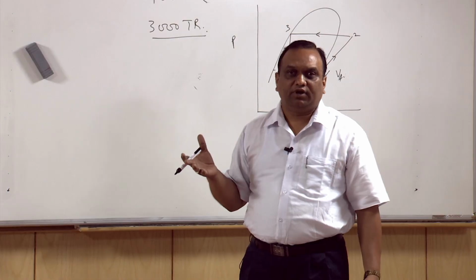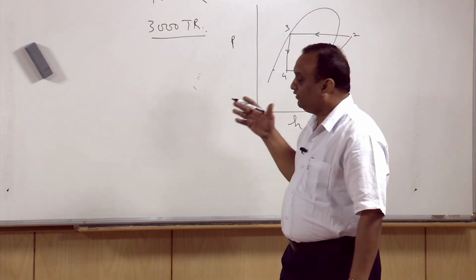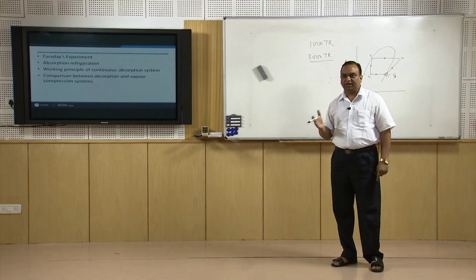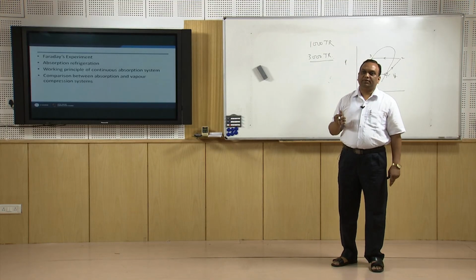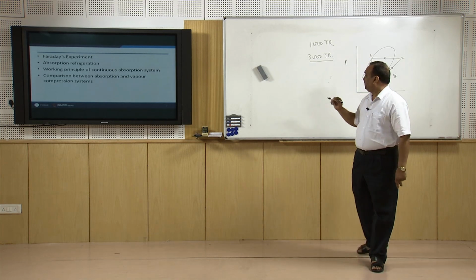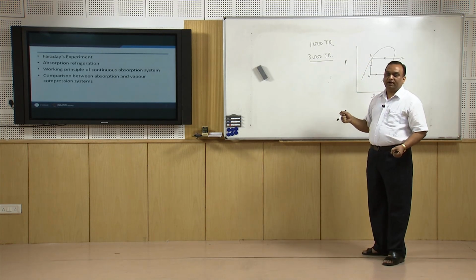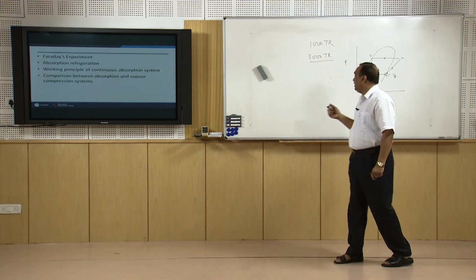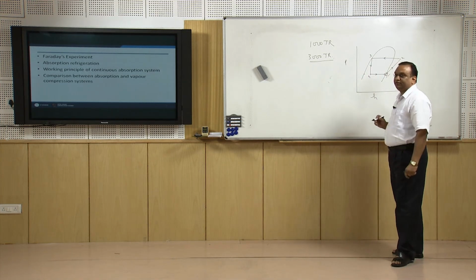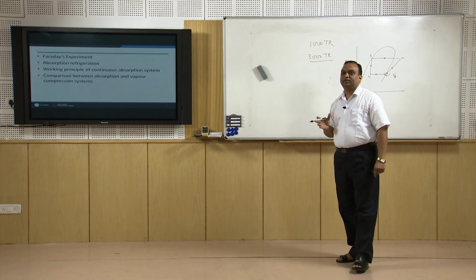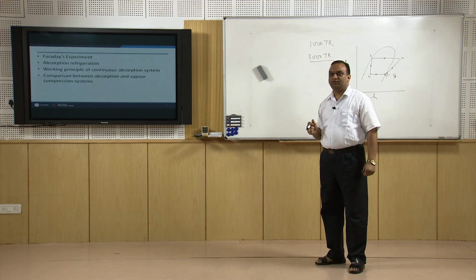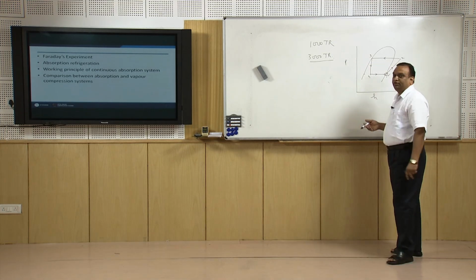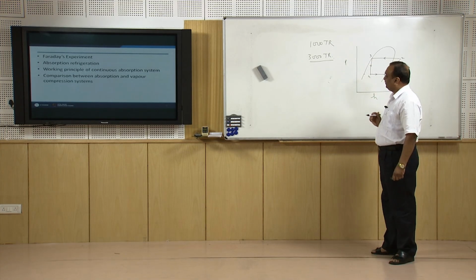Suppose I am using a reciprocating compressor. In that case, reciprocating compressors are not fully balanced. Some unbalanced force will be there that will create vibrations. Strong foundations will be required. In addition to that, if I am using a rotary compressor, normally to handle large volumes, rotary compressors are used. So rotary compressors will also require a very strong foundation. Size of the compressor will be very large. And the cost of this plant will also be high.